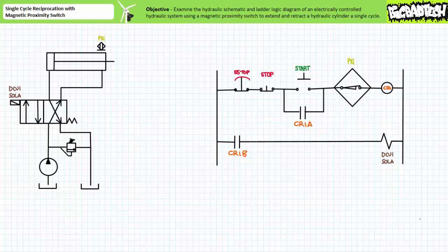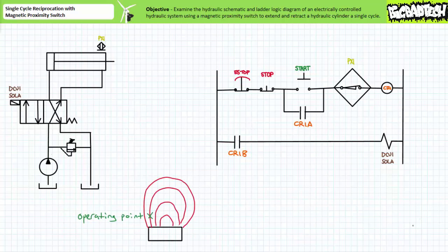The magnetic proximity switch associated with this contact also appears in the hydraulic schematic as a diamond mounted on the barrel of the cylinder. Two important points exist inside the magnetic proximity switch's range. When a magnetic object enters the operating point the associated contacts change to their opposite states — in this case our normally closed contact will open. Upon leaving the release point the switch returns to its deactivated state and our normally closed contact will reclose.